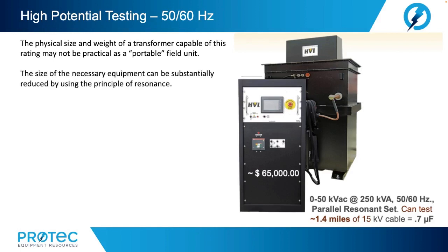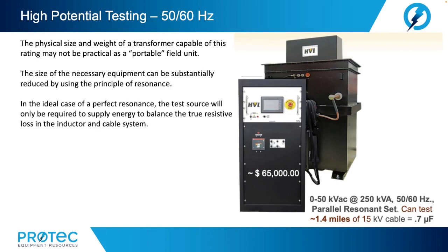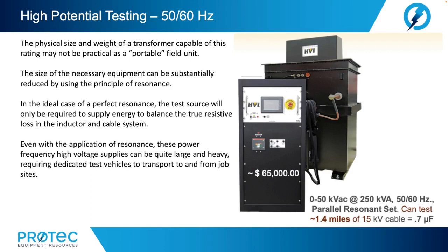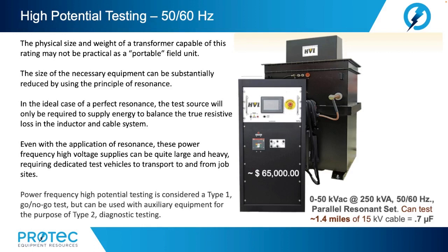The size of the necessary equipment can be substantially reduced by using the principles of resonance. In the ideal case of a perfect resonance, the test source will only be required to supply energy to balance the true resistive loss in the inductor and cable system. Even with the application of resonance, however, these power frequency high voltage supplies can be quite large and heavy, requiring dedicated test vehicles to transport to and from the job sites. Power frequency high potential testing is considered a type 1 go, no-go test, but it can be used with auxiliary equipment for the purposes of type 2 diagnostic testing.